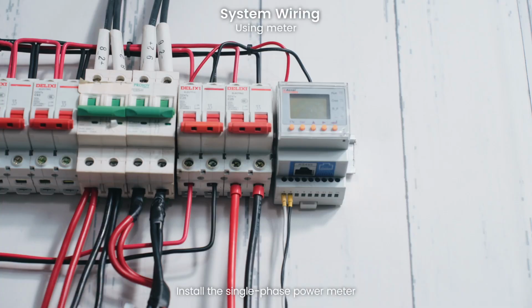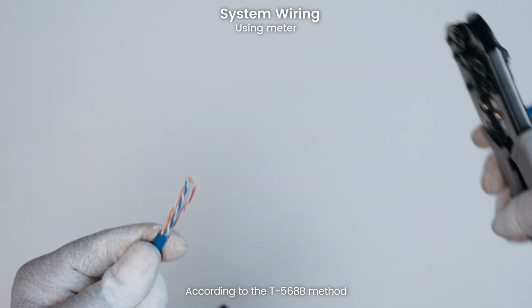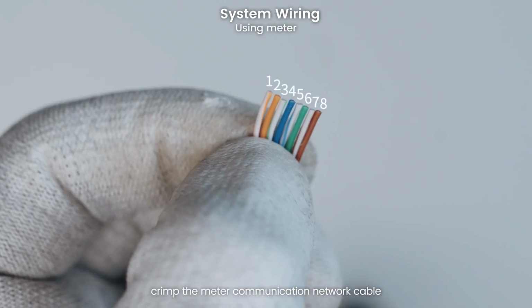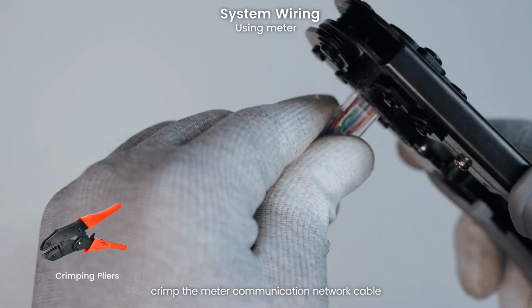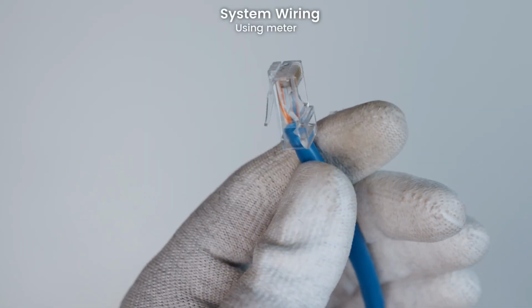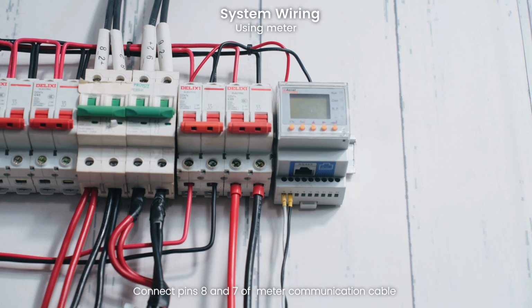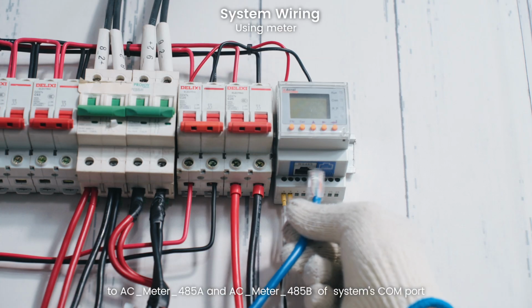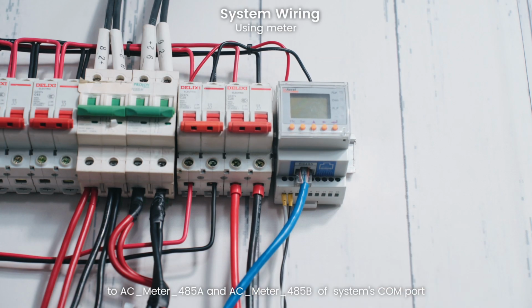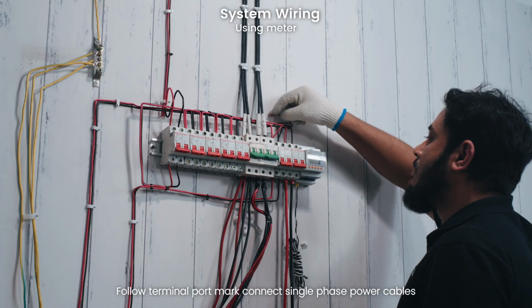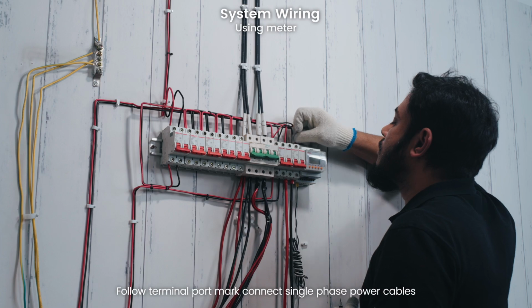Install the single-phase power meter. According to the T568B method, crimp the meter communication network cable. Connect pins 8 and 7 of meter communication cable to AC meter 485A and AC meter 485B of the system's COM ports. Follow terminal port mark to connect single-phase power cables.